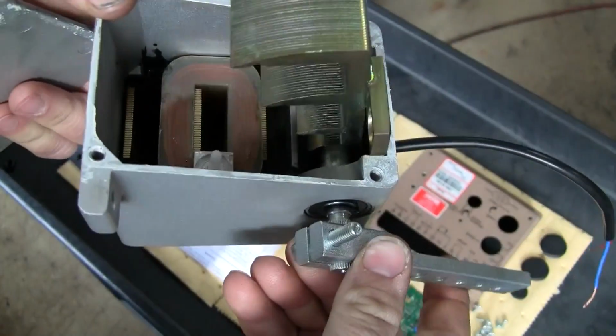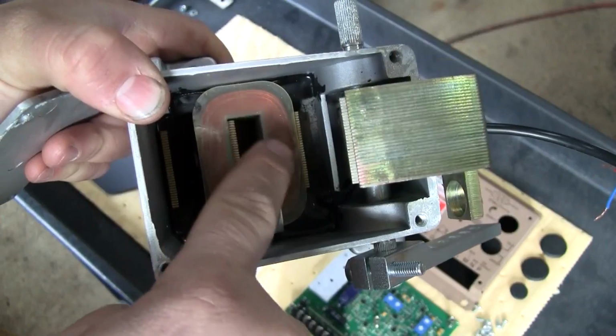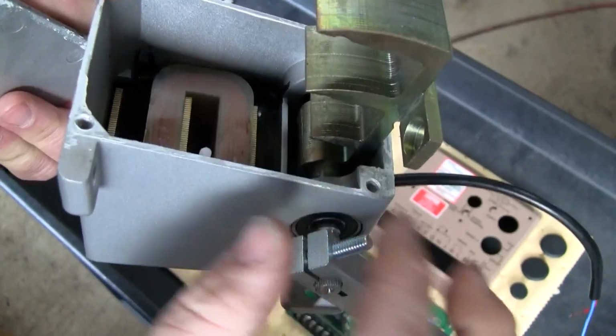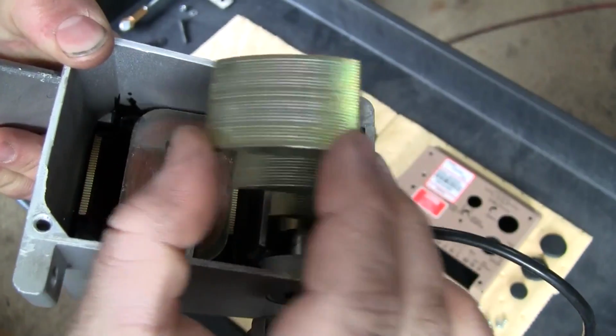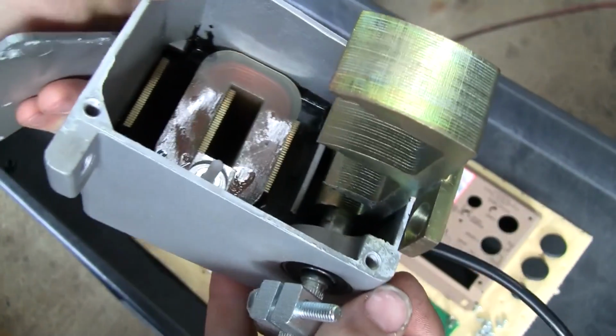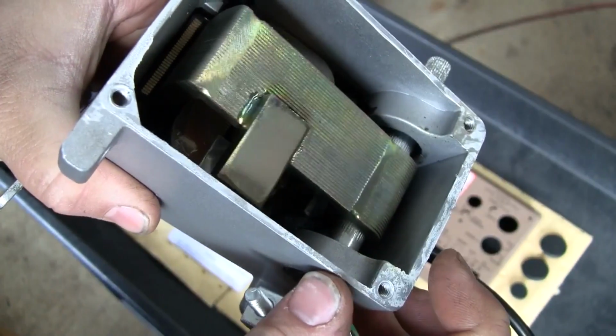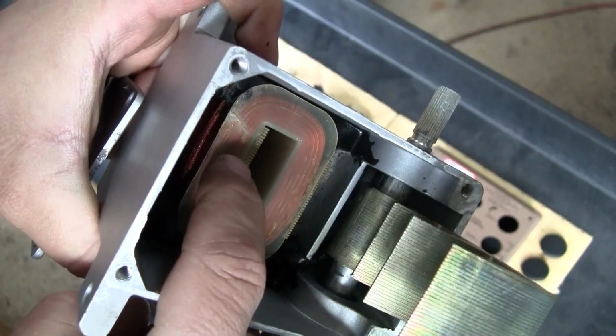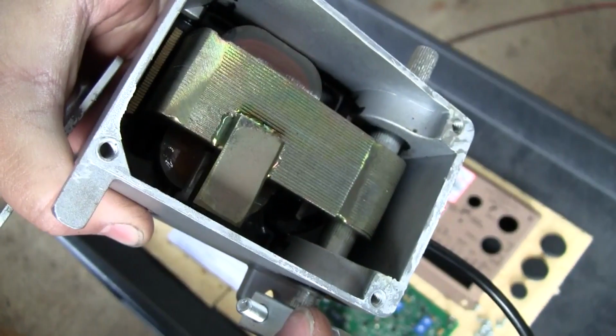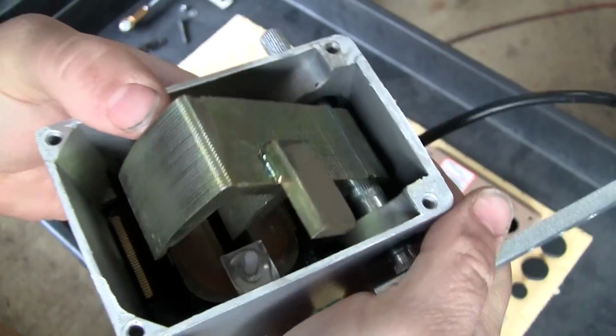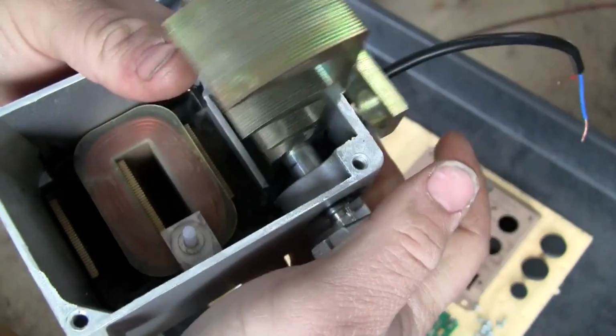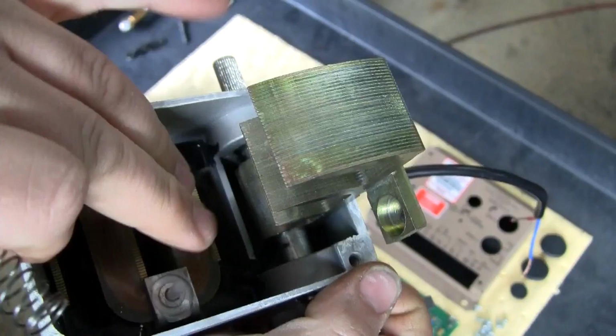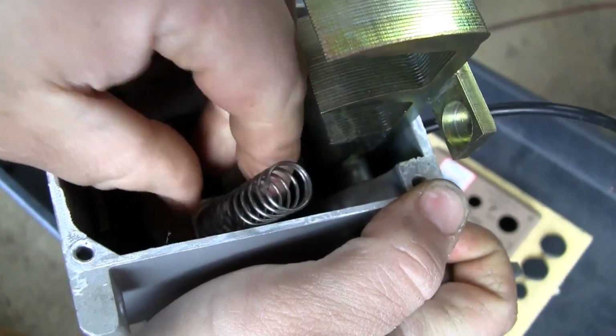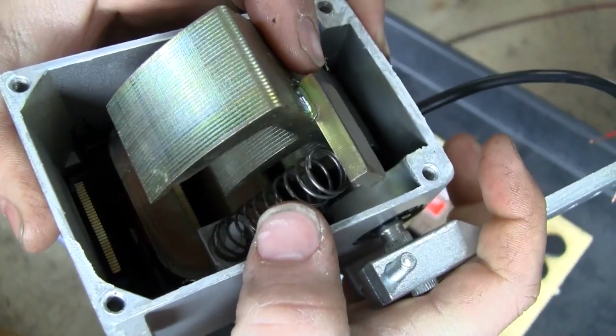If it's not a stepper motor type actuator, it's essentially just this. You've got a coil here on an armature, and then you've got a movable - what would you call that - a movable armature, laminated steel core that is pulled in and out. The harder you energize this coil, the greater the magnetic field strength, the more it wants to pull this plunger into the field. Oop, just dropped that. Then you've got a stop here, a little nylon stop, and then there's a spring that sits in this pocket here and on around that stop. So something like that - it's a spring return actuator.